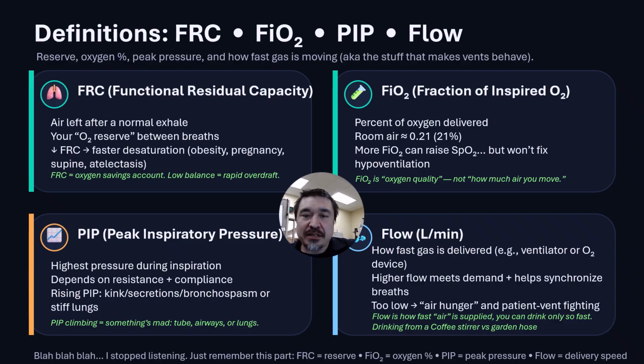And then finally, flow. Now this is not to be confused with the O2 setting on your tank. This is how much flow of air you would need to take a breath. It's like if you were underwater, would you be breathing like you're trying to get air through a straw, or would you prefer a traditional snorkel? A peak inspiratory flow could be 20 to 30 liters per minute for an average adult when calm, 40 to 60 when they're in mild distress, and in excess of 100 to 150 when they're gasping for air.